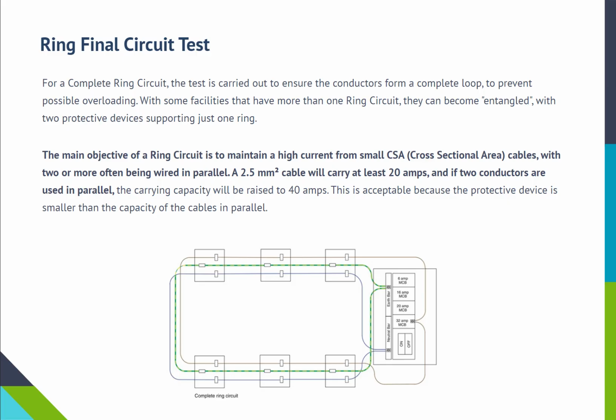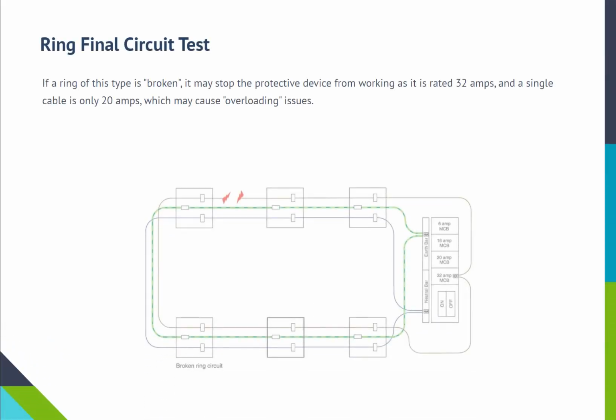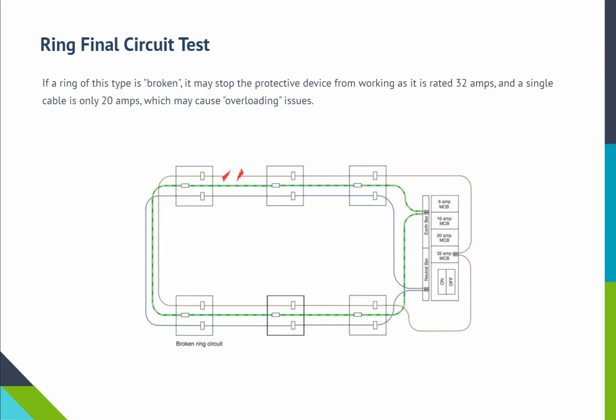A 2.5 mm square cable will carry at least 20 amps, and if two conductors are used in parallel, the carrying capacity will be raised to 40 amps. This is acceptable because the protective device is smaller than the capacity of the cables in parallel. If a ring of this type is broken, it may stop the protective device from working as it is rated 32 amps, and a single cable is only 20 amps, which may cause overloading issues.